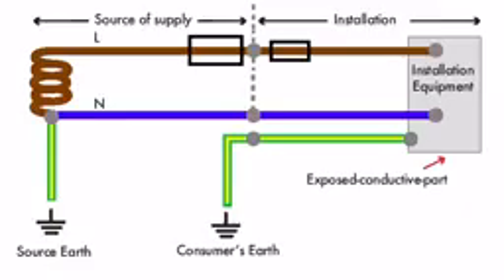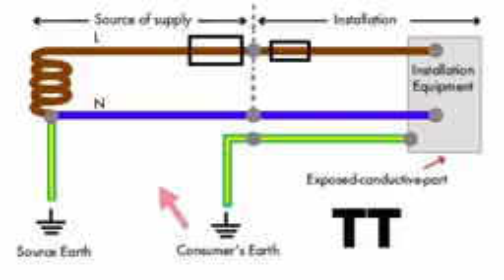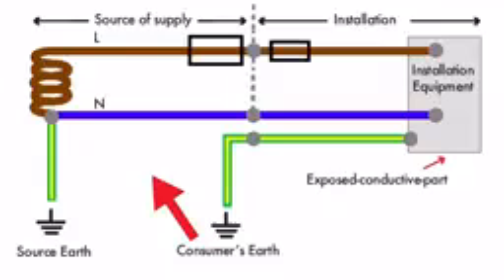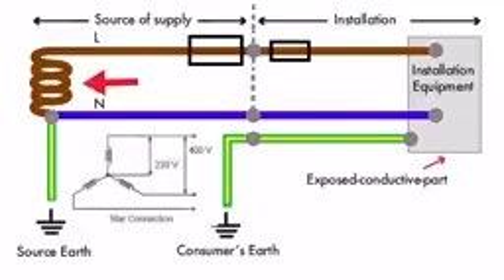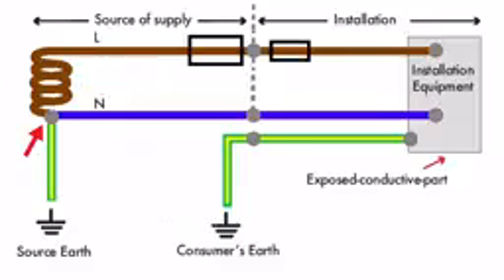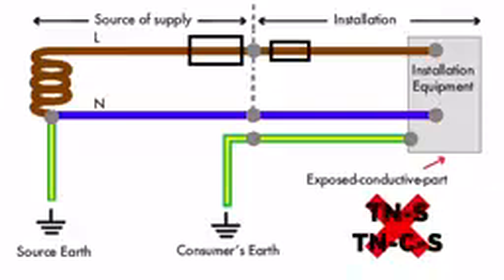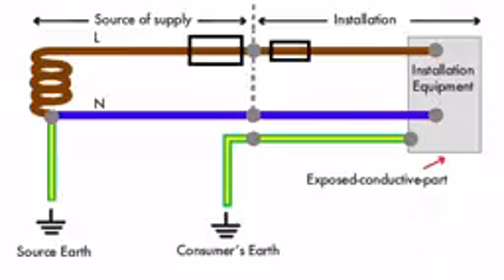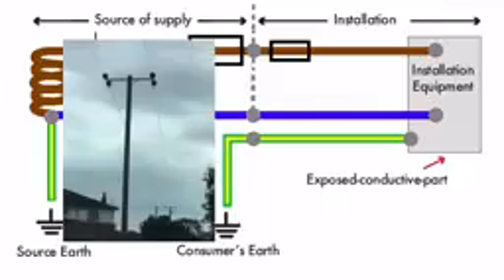TT earthing arrangements. The left hand side of this drawing shows the supply authority's cable. In this earthing arrangement, the supply authority will only provide you with line and neutral conductors to a single phase installation. On the supply authority side, this drawing only shows one of the 3 star connected windings as well as the centre tap point to earth. TT earthing arrangements are often given to buildings that are remote, where it would be uneconomical for the supply authority to provide either TNS or TNCS earthing arrangements. The TT supply is likely to be coming into the installation overhead.